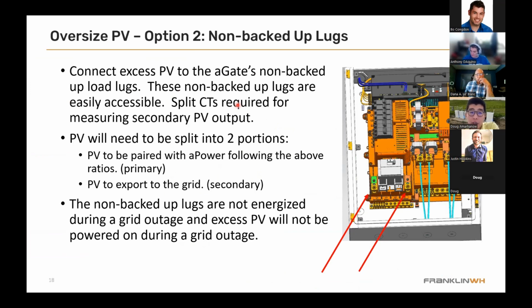Additional low-cost options are to connect the PV, instead of using the AP box, to these non-backed-up lugs. There are ways around it. You're going to have to follow some wiring—it's a little more complicated in terms of wiring, but the cost is basically the same as using the AP box. Actually a little cheaper if you don't want to purchase the AP box. There's more labor involved, and you have to put on a couple of CTs to track that extra PV going to the non-backed-up lugs, to make sure it's being tracked into the system.